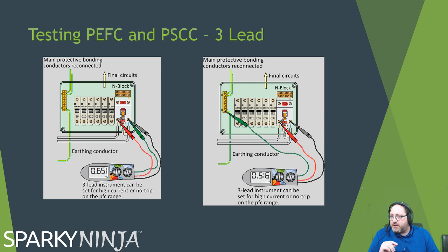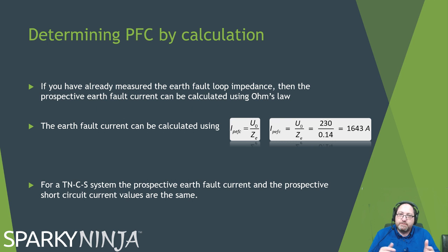The alternative to measurement is calculation, because we can, but we shouldn't. If you've already measured earth fault loop impedance, then the prospective earth fault current can be calculated using Ohm's law. The earth fault current can be calculated using I equals UO over ZE. That's Ohm's law.